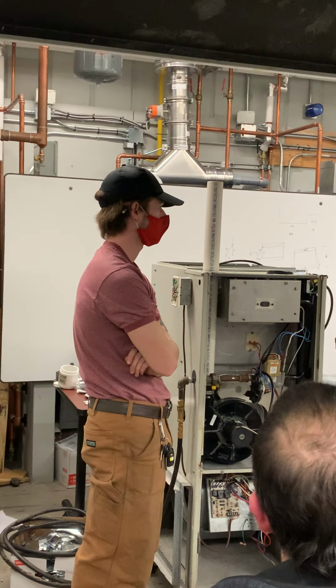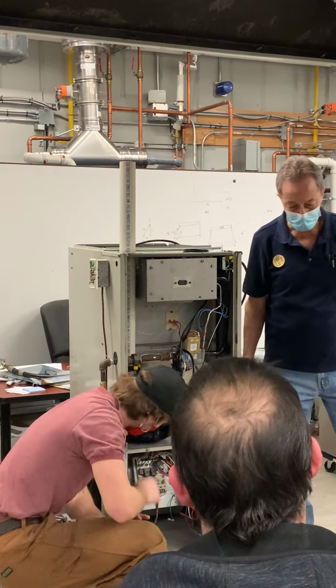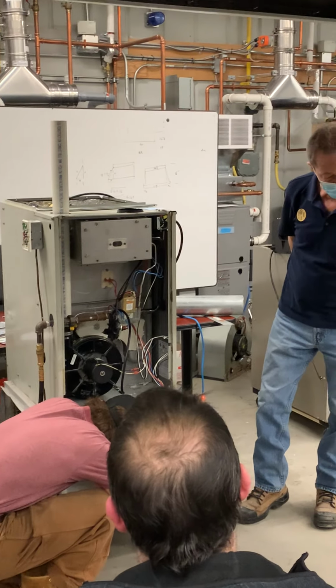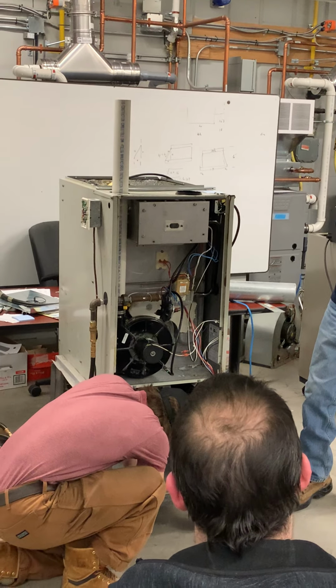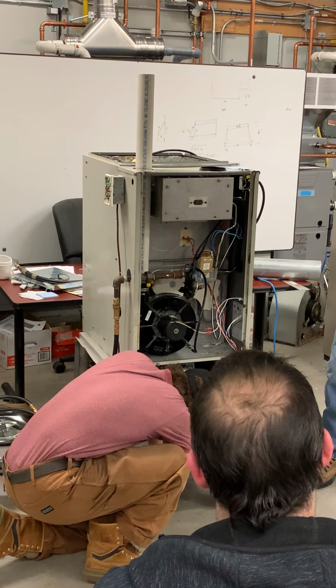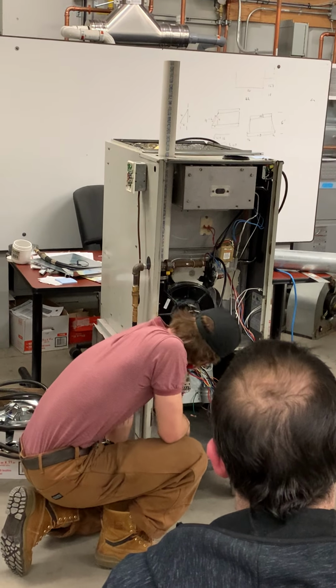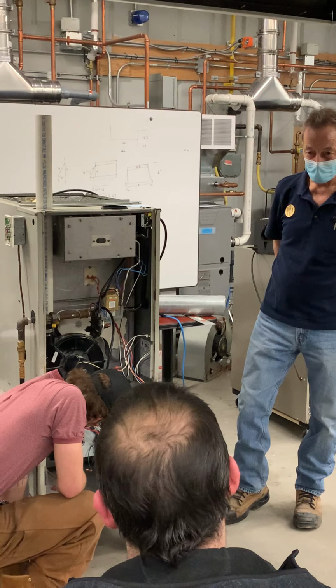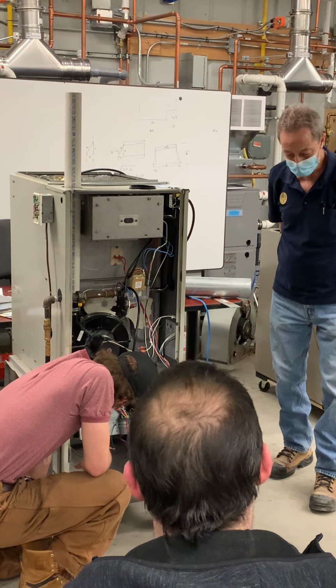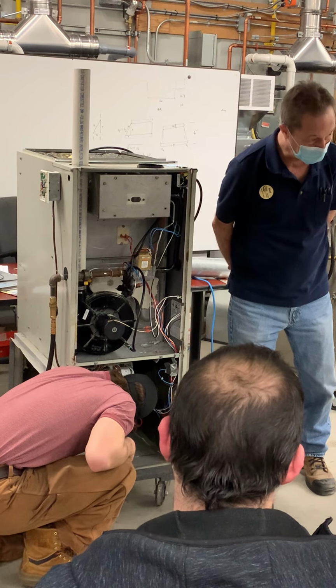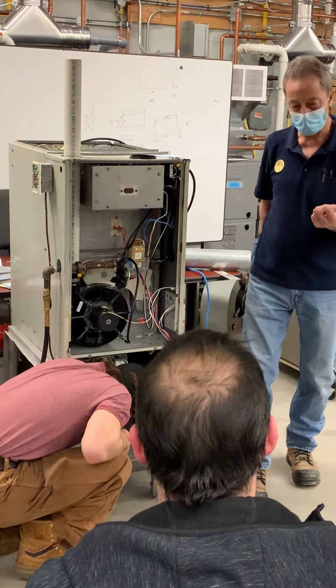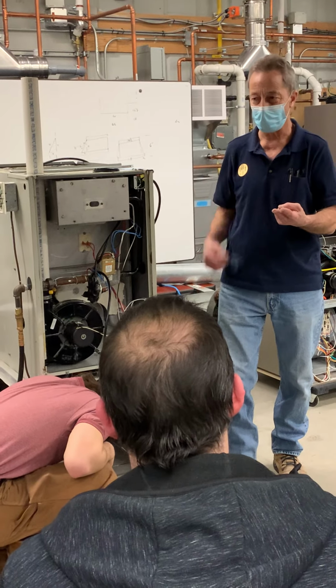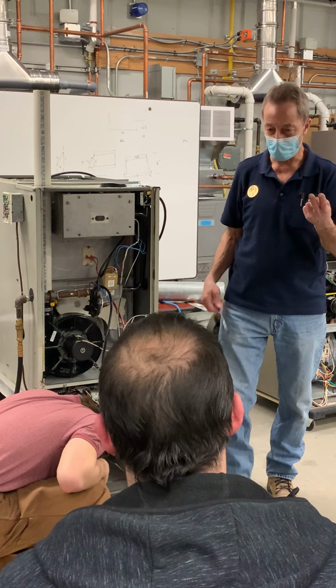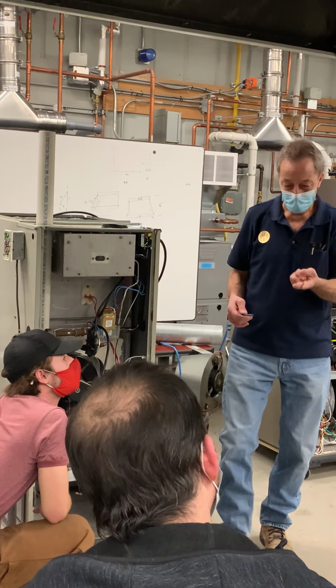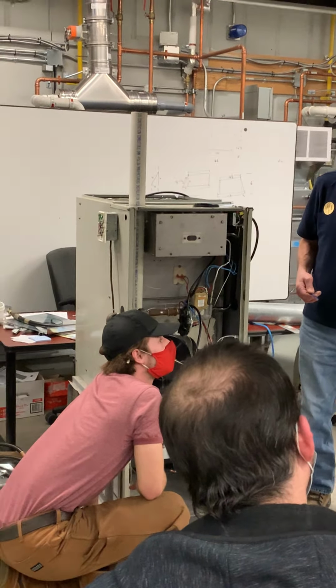On this one here, can you get on your knees, please? Look at the circuit board, look at the lower left, and what do you see? The little switches? Yes, what do we call those switches? DIP switch, which stands for dual inline package. How many switches are on the DIP switch combination there? There's 3. Can I give you a hint? 2 of those DIP switches are for fan off delay. If 2 of them are for the fan off delay, how many possible timings are there for fan off? Say 4, please. 4. Because 2 switches could be up, that gives me 1 time. 2 switches could be down, that gives me another time.